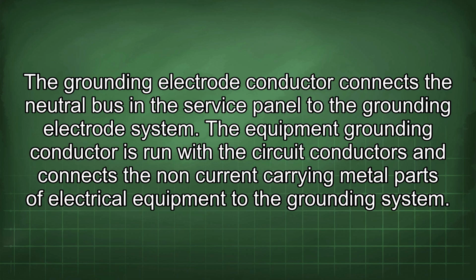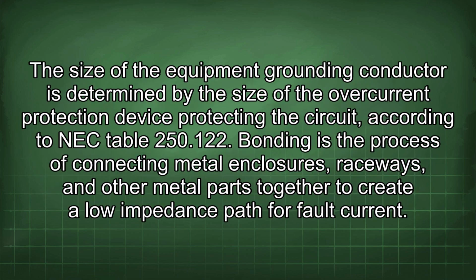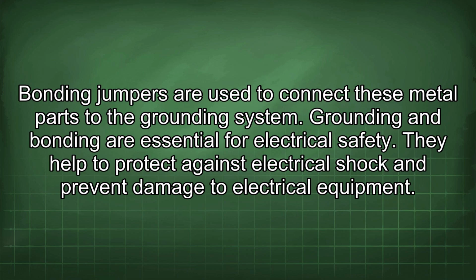The equipment grounding conductor is run with the circuit conductors and connects the non-current carrying metal parts of electrical equipment to the grounding system. The size of the equipment grounding conductor is determined by the size of the overcurrent protection device protecting the circuit, according to NEC Table 250.122. Bonding is the process of connecting metal enclosures, raceways, and other metal parts together to create a low impedance path for fault current. Bonding jumpers are used to connect these metal parts to the grounding system.